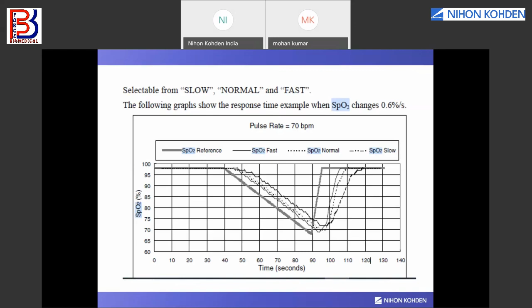There could be other frequent operational problems that can be seen in SpO2, like unstable SpO2 value. Check the probe. As we mentioned, the probe size could be inappropriate. Change the probe size. The probe may be attached to the same limb that is used for NIBP. When NIBP is taken, there is constriction in the artery, so the SpO2 reading will not come, or it is an erratic SpO2 reading. Attach this SpO2 probe to the other limb, not the same limb as the NIBP cuff.